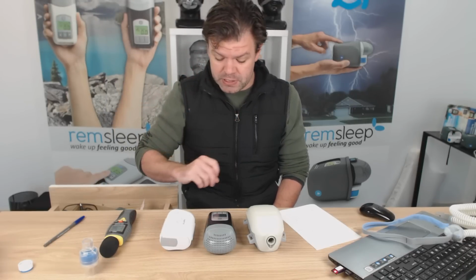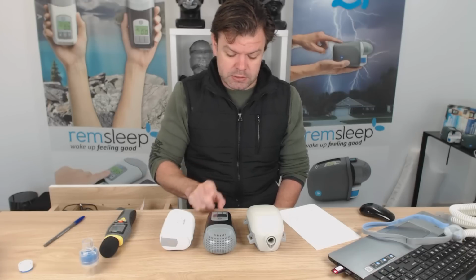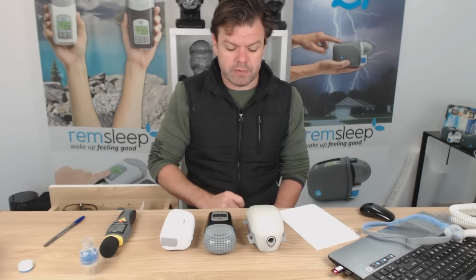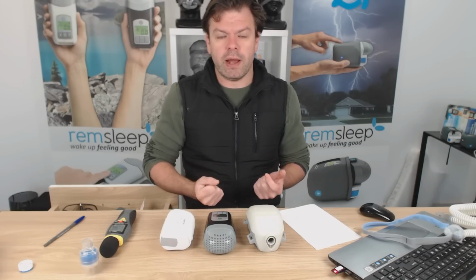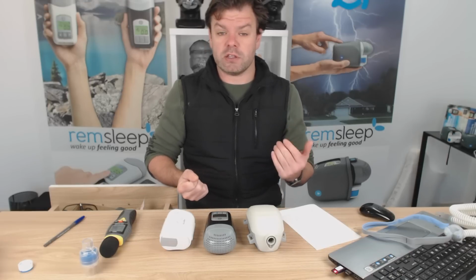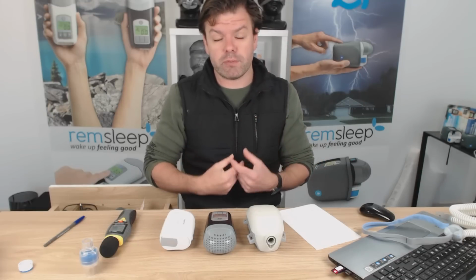It also has the smart ramp, which means the machine will stay nice and low until you fall asleep. It can detect your sleep onset and then adjust upwards accordingly. That's the ResMed - these two don't have a smart ramp, they've just got a standard ramp. To be honest, most of the auto algorithms are pretty good anyway, and they will just stay nice and low when you're awake because you're not having sleep apnea, and then when you start having sleep apnea, they will go up as your breathing starts to become restricted.